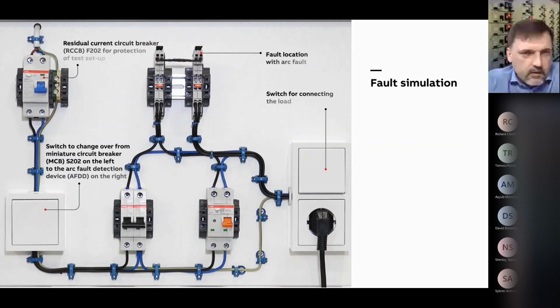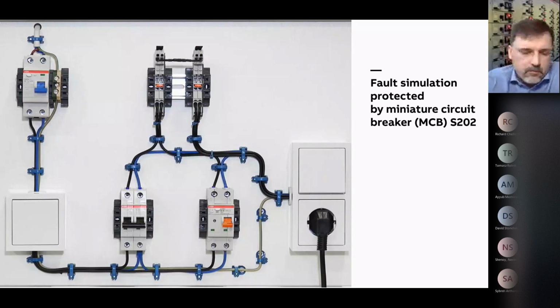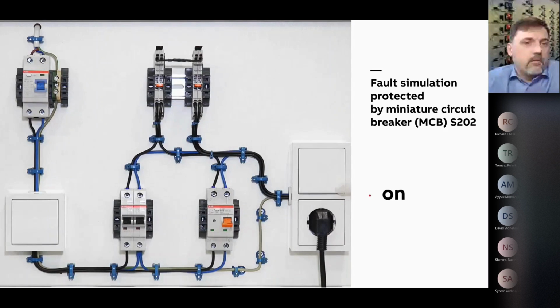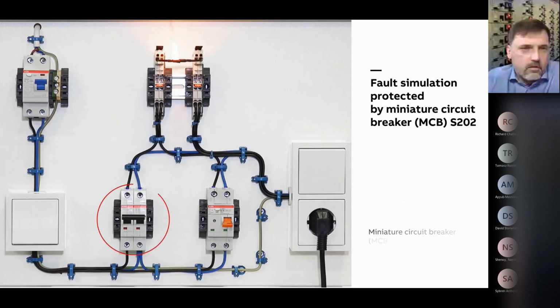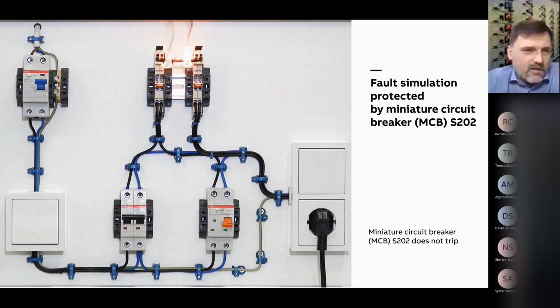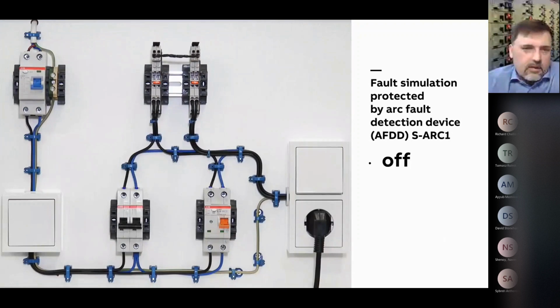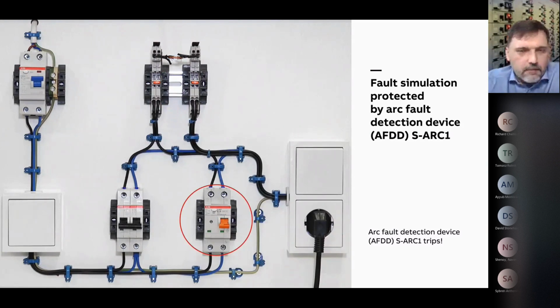Because the energies are usually small enough, of course if you grab it, it will harm you, but it's not a risk for you from an arc flash point of view. It's a very big risk from a fire point of view. And those systems are designed in a way that will prevent fire in commercial installations, and they do it significantly. So, yeah, and I like this video actually from it. It explains it very well. I don't have to add too much to it. The difference is that the AFDD, the arc fault detection device, has electronics inside. It looks similar, but it's not the same thing.